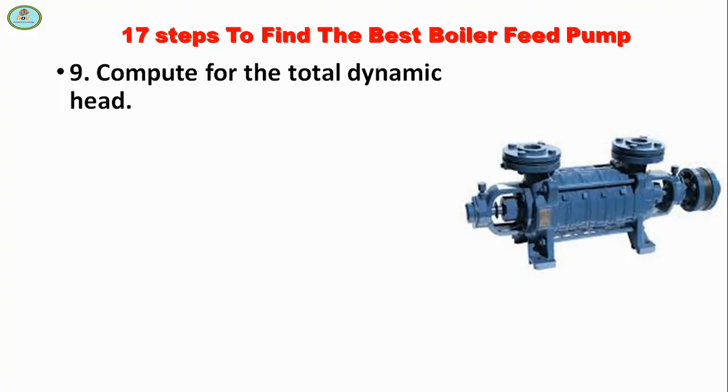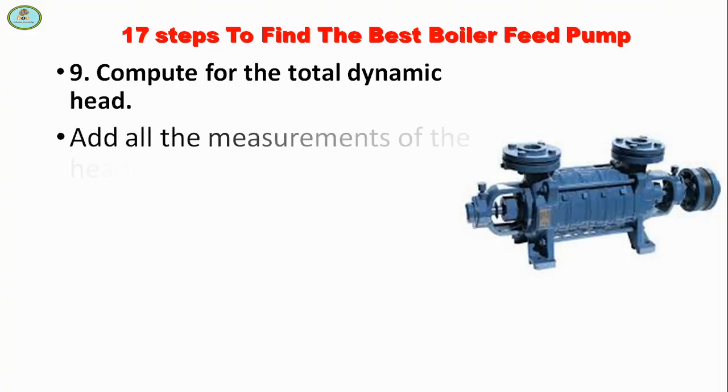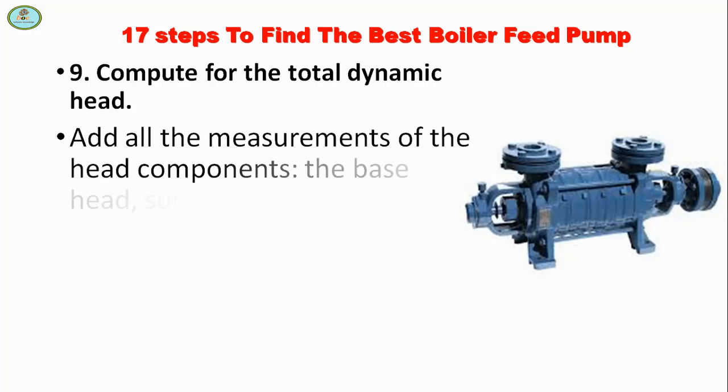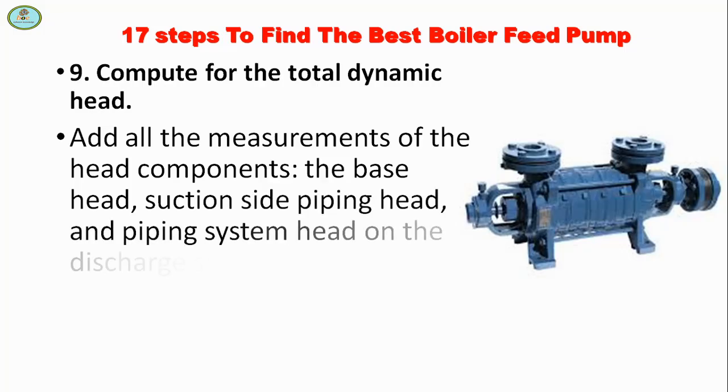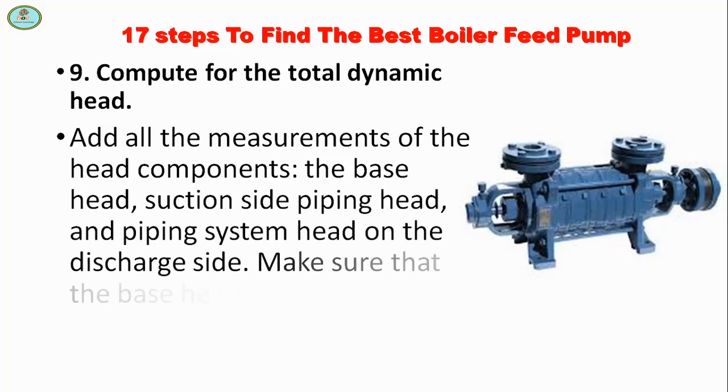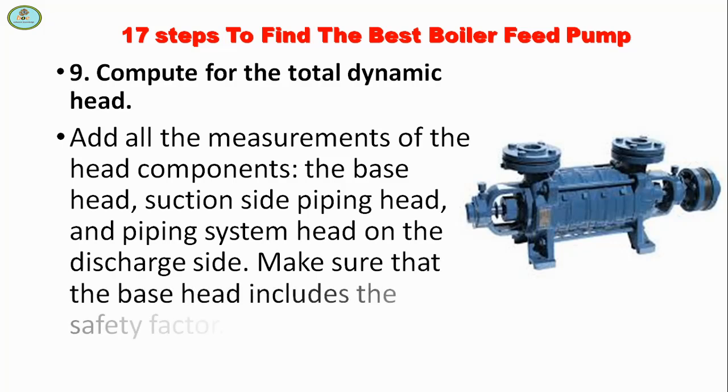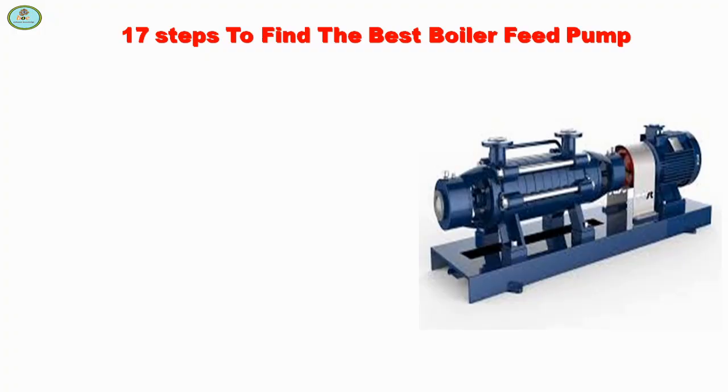Compute for the total dynamic head. Add all the measurements of the head components: the base head, suction side piping head, and piping system head on the discharge side. Make sure that the base head includes the safety factor.